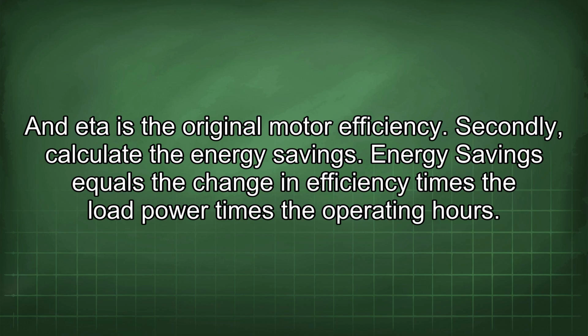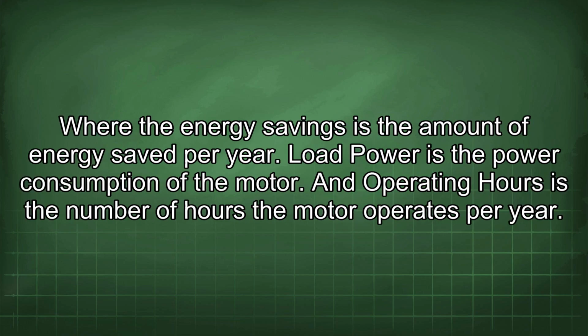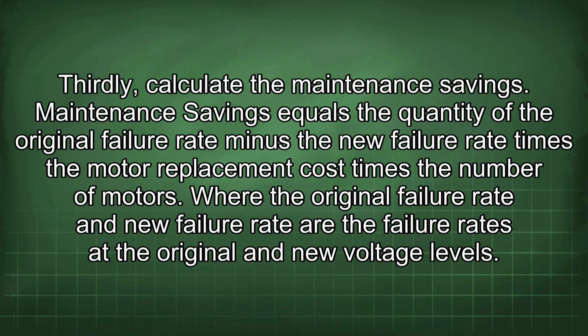Secondly, calculate the energy savings. Energy savings equals the change in efficiency times the load power times the operating hours, where the energy savings is the amount of energy saved per year. Load power is the power consumption of the motor, and operating hours is the number of hours the motor operates per year. Thirdly, calculate the maintenance savings.